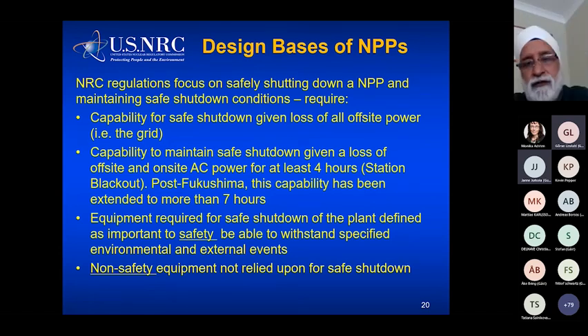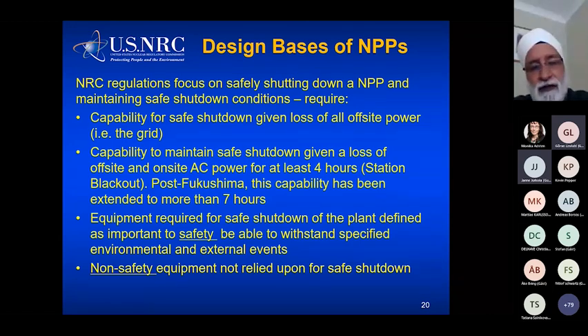What's the design basis of the nuclear power plants? Typical, right? We know we have the capability for safely shutting down given the loss of offsite power. We know we can maintain safe shutdown conditions given total loss of on-site and off-site power for at least 4 hours. In other words, if the diesel, somewhat EDG, is somewhat reluctant to start, or damaged but can be repaired, we can last 4 to 6 or 7 hours without AC power.